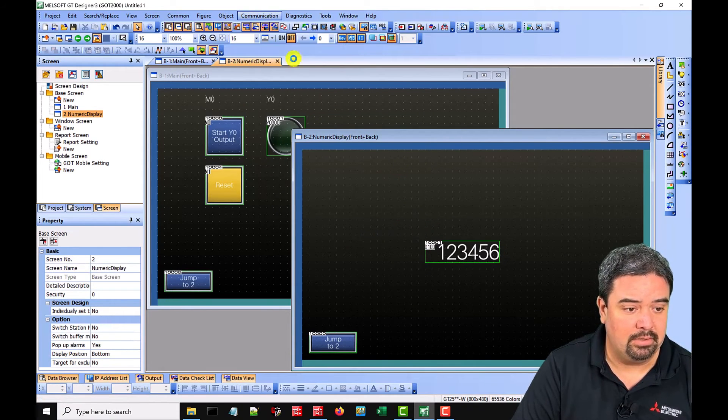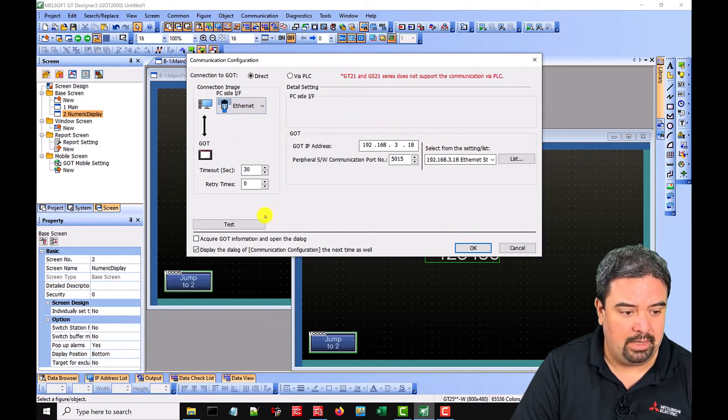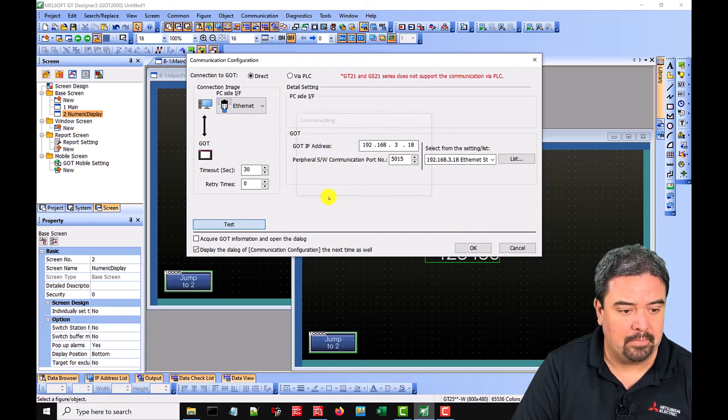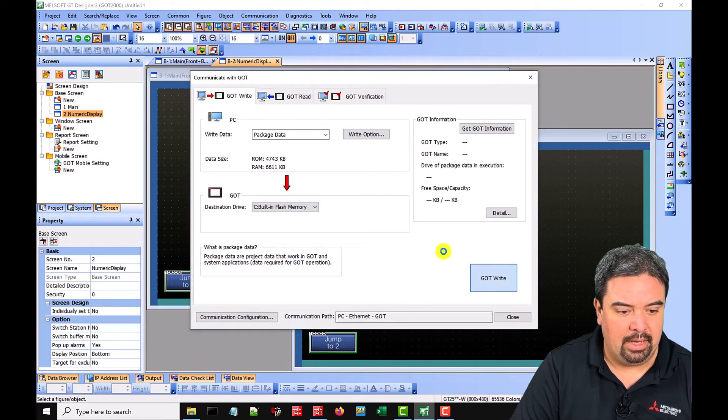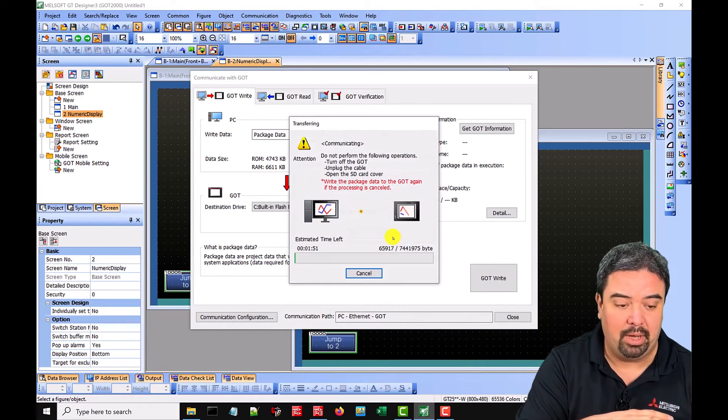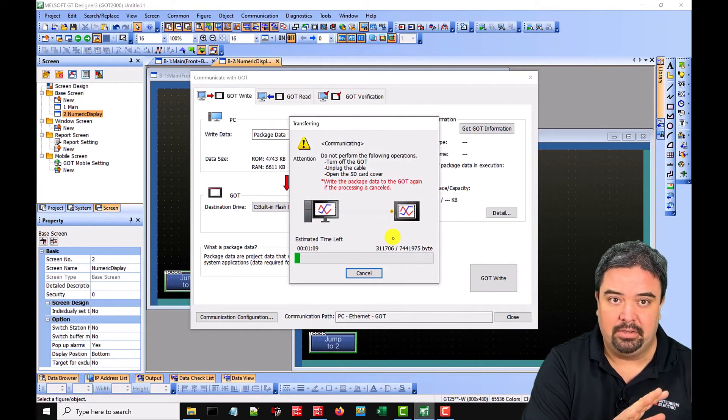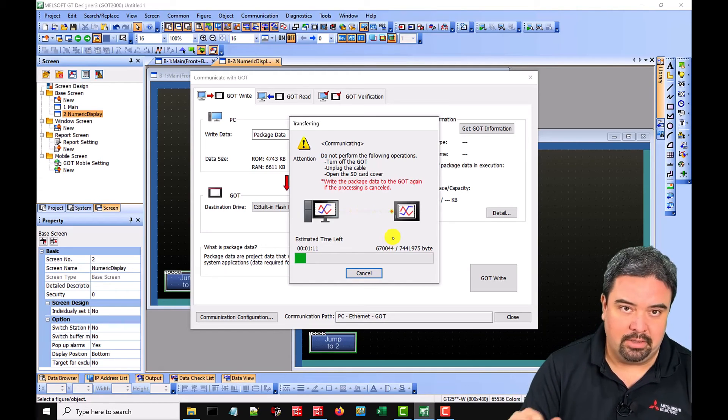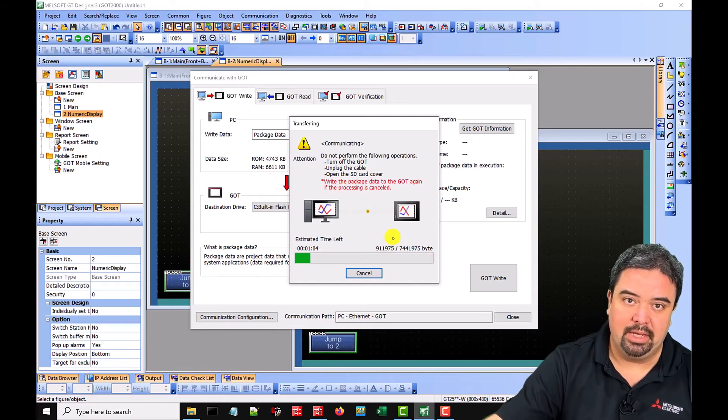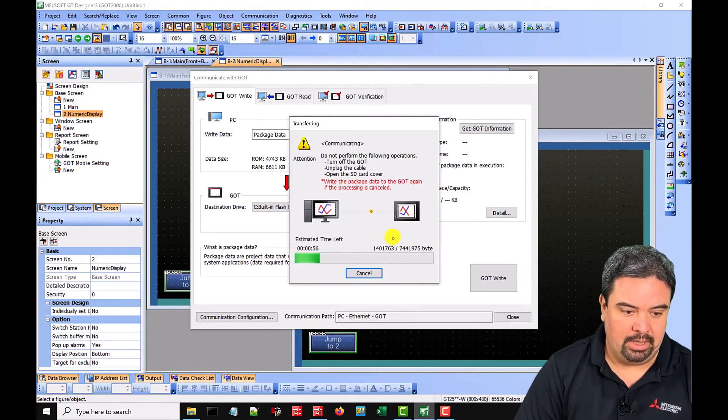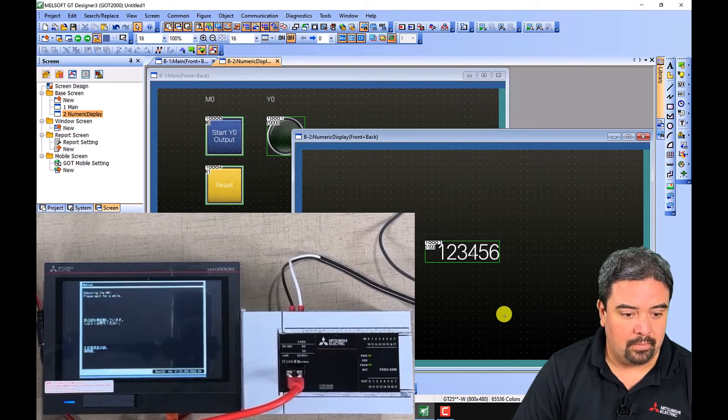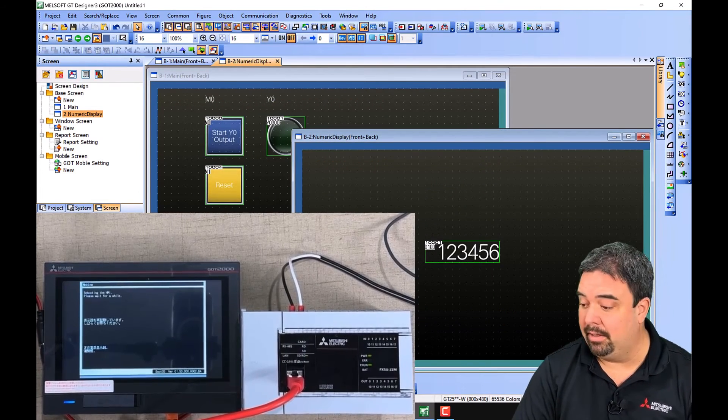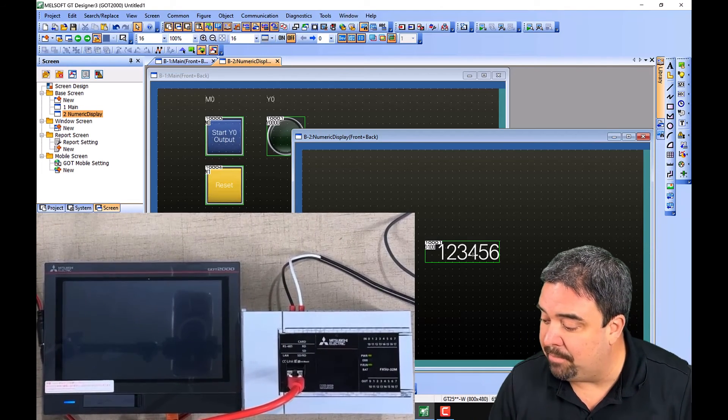So communication write to GOT. We'll change this to ethernet 3.18, we can do a test. We have successful connection and click okay and write. So what's really nice about the software, we don't have to do an offline compile and write. We can just make changes and immediately write. Now this first time around it's going to take a little while because what it's doing is updating the OS and it's writing the driver, the ethernet driver, and everything else we need. And just like that everything has been written and the GOT will reset.